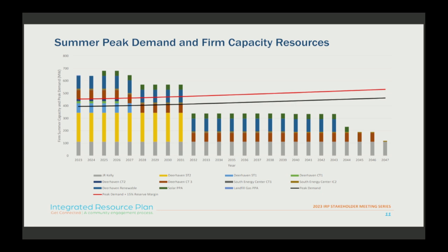I do want to say, though, that this line does represent what we think is the load forecast going out, taking into consideration all of those things like demand side management, like energy efficiency. When we looked at DSM programs across the nation, large and small utilities, the impact on the peak overall was very small, less than 5%, in most cases less than 1%. So you're looking at a 0.5% to 1.5% change in your peak output for DSM, for conservation, and so forth. We were a little surprised by that, but that information was consistent. And actually 2% is very, very high.